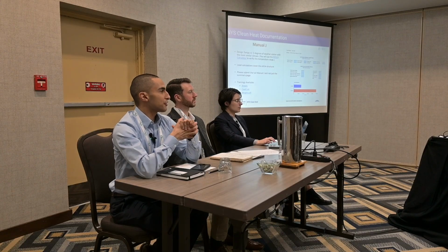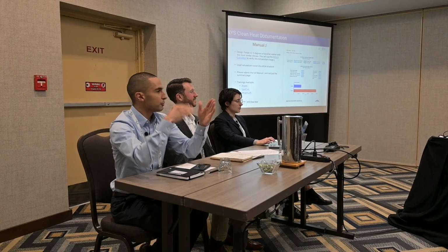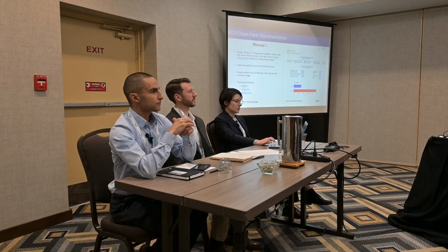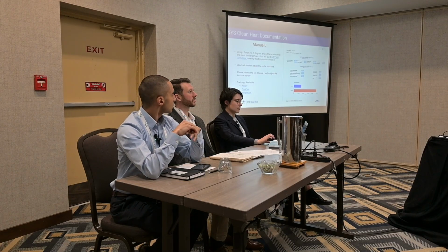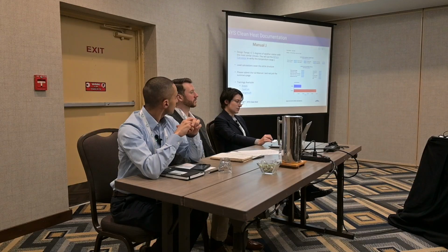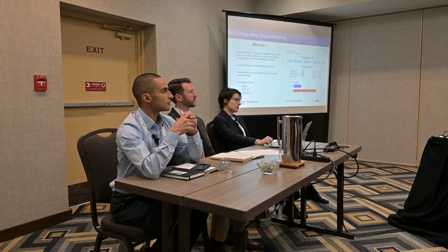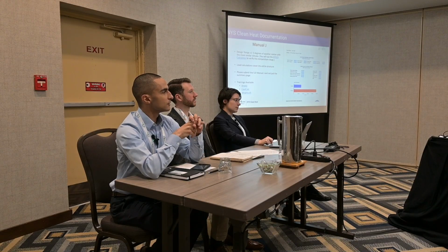Right. If you're very slightly under, like 99%, we can discuss, but typically we prefer that you go a little bit over than a little bit under. Okay. Yeah, I would only add, the design temperature variance often does accommodate small percentages below 100%. So we allow plus or minus 5 degrees on the design temperature. If you're within 1%, you'd probably rather see the design temperature adjusted than the next size system installed. It's really case by case.